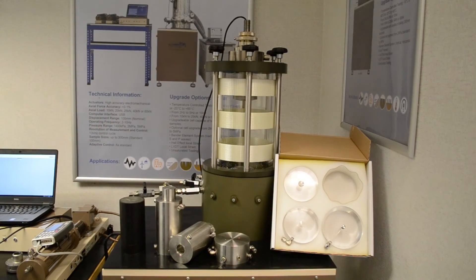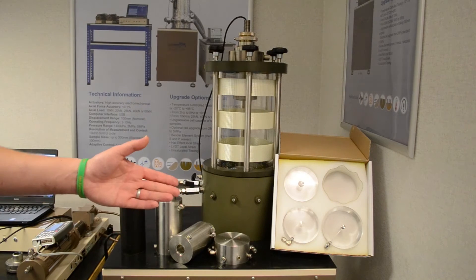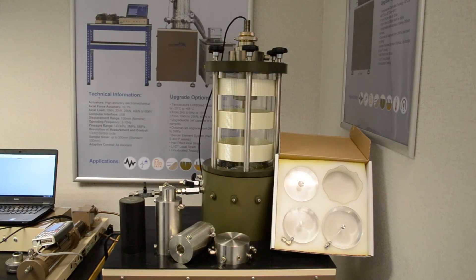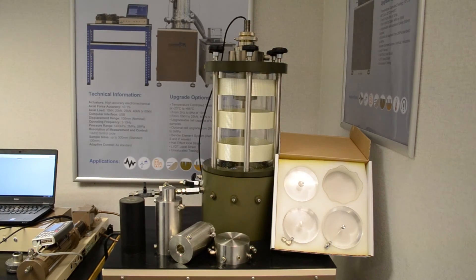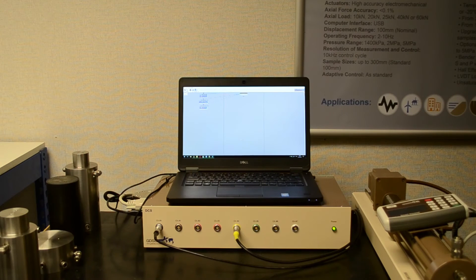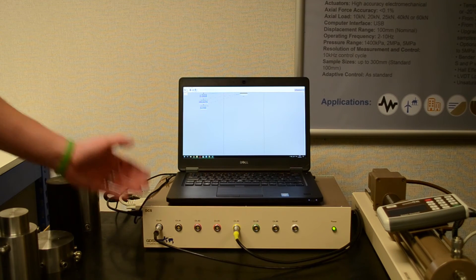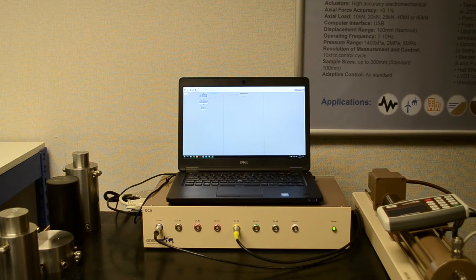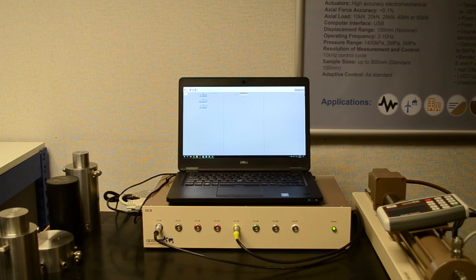Here we have a sample of the pedestals and top caps that can be used with the system. The standard system supports samples up to a diameter of 100 millimetres and a height of 200 millimetres. The standard system comes with an eight-channel high-speed data acquisition unit that both controls the system and records the data from the transducers that are connected via the GDS software, GDS Lab.